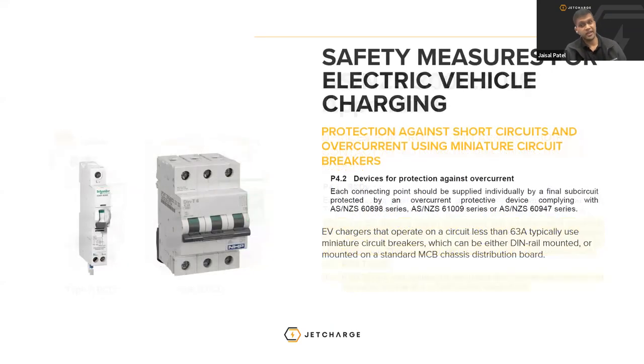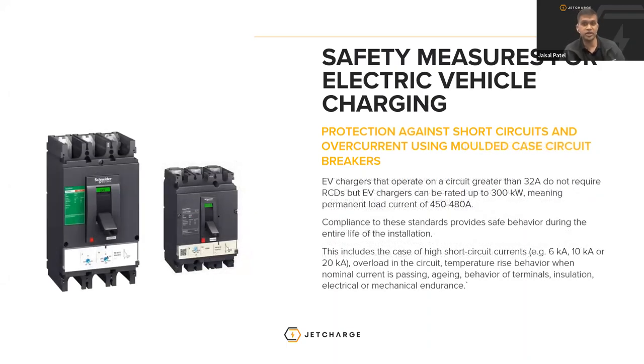Obviously, the other step that you have to take into consideration is protection against short circuit or overcurrent using an MCB, or miniature circuit breaker. Each connecting point should be supplied individually by a final subcircuit protected by an overcurrent protective device, complying with AS60898 and its other series. EV chargers that typically operate on a circuit less than 63 amps use miniature circuit breakers. So it's very easy to install a circuit breaker with a type A RCD that fits on a typical MCB chassis, or they can also be DIN rail mounted if you have a DIN rail mounted board. Next slide.